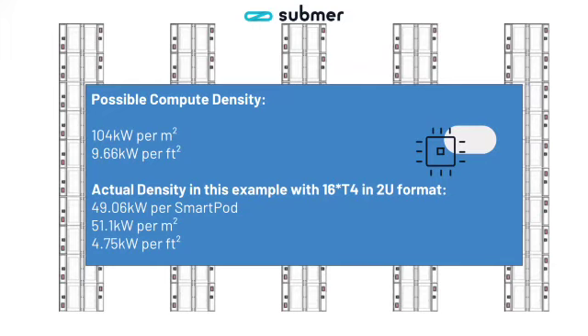I'm communicating from my side a density possibility of 104 kilowatts per square meter, or 9.66 kilowatts per square foot. The actual density represented in this particular example is actually about 51.1 kilowatts per square meter, or 4.75 kilowatts per square foot. And it gives us something like 2.2 to 2.4 kilowatts per U.